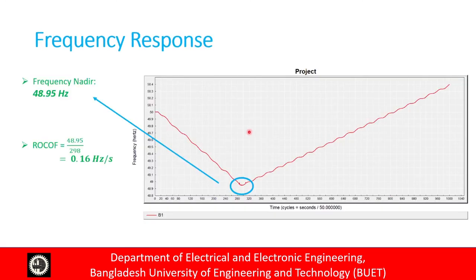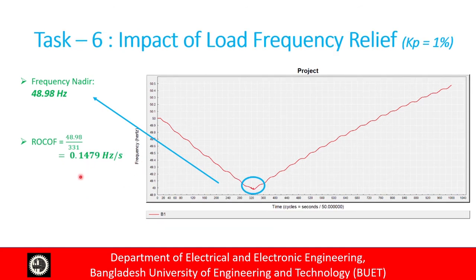Looking at the frequency response with the zoning scheme, for kp equal to zero we get a frequency nadir of 48.95 Hz and RoCoF of 0.16 Hz/s. Before zoning-based load shedding, the frequency nadir was 49.4 Hz, and after zone-based load shedding we can see improvement in the frequency nadir. In Task 6, we investigate the impact of load frequency relief, varying kp from 1% to 3%. For kp equal to 1%, the frequency nadir is 48.98 Hz and the RoCoF is 0.1479 Hz/s.